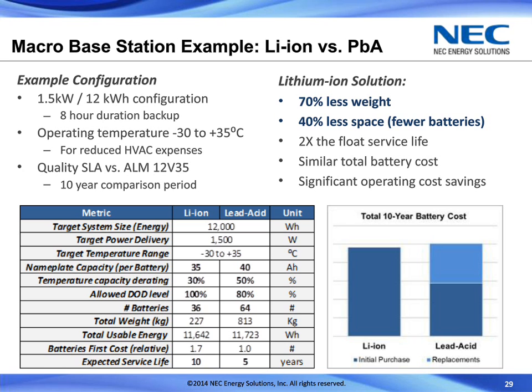And due to that oversizing, you get the pretty big weight difference, 227 kilograms versus 813 for the lead. The usable energy ends up about the same, which is the whole point of the exercise, oversizing the lead, which you have to do to support the application. So with this, the upfront cost is a little bit more for the lithium, no surprise, about 70% higher. And then that last piece of the puzzle of cost is the service life.